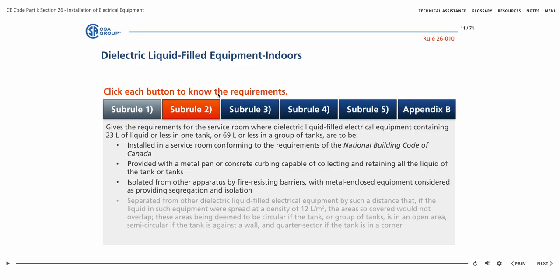and separated from other dielectric liquid-filled electrical equipment by such a distance that, if the liquid in such equipment were spread at a density of 12 liters per square meter, the areas so covered would not overlap, these areas being deemed to be circular if the tank or group of tanks is in an open area, semicircular if the tank is against the wall, and quarter sector if the tank is in a corner.